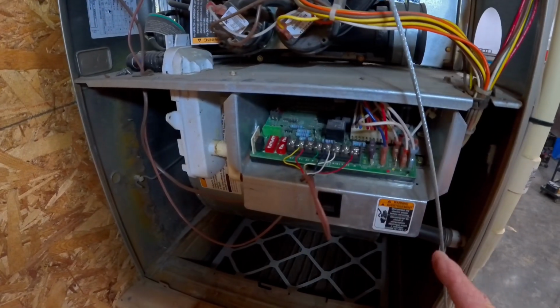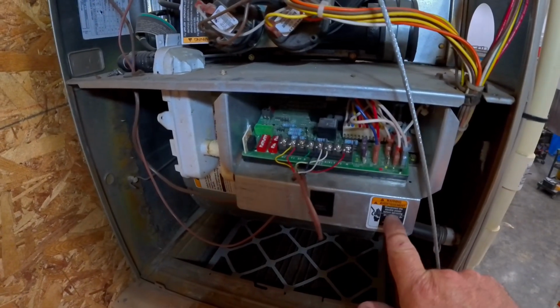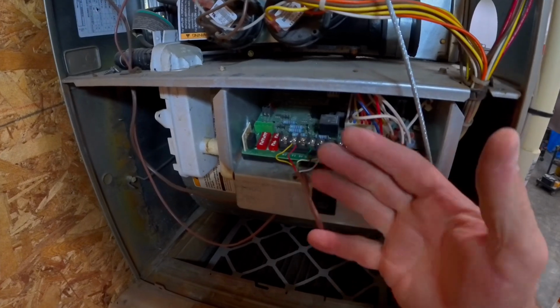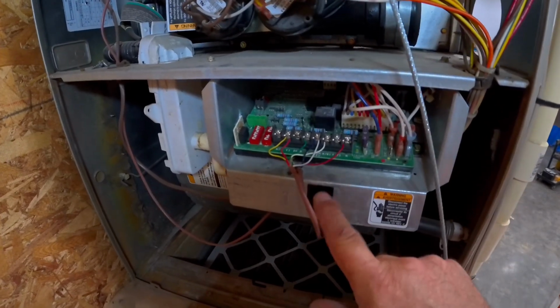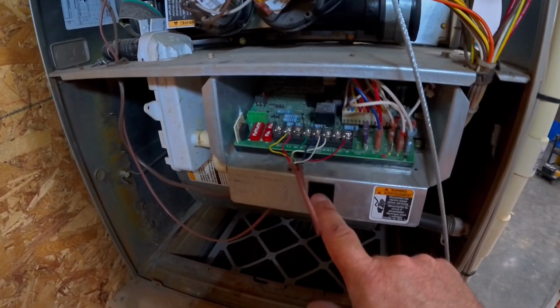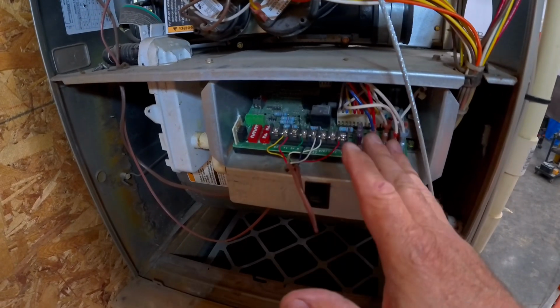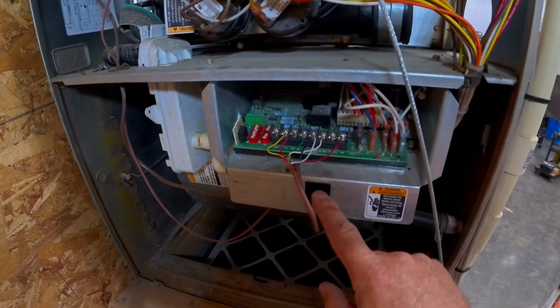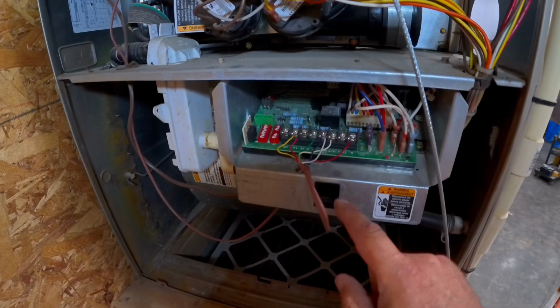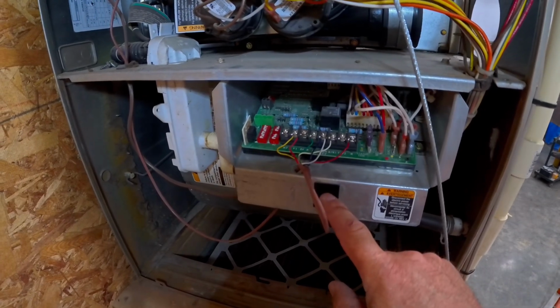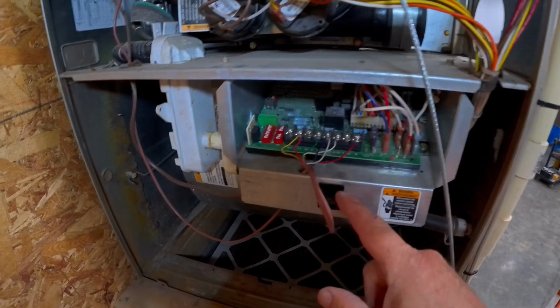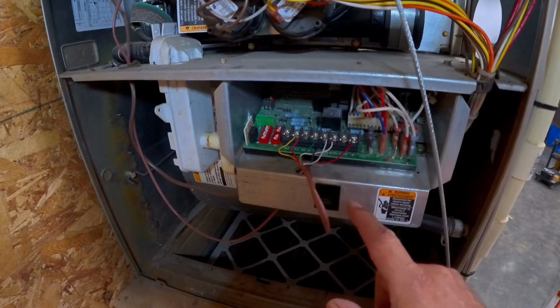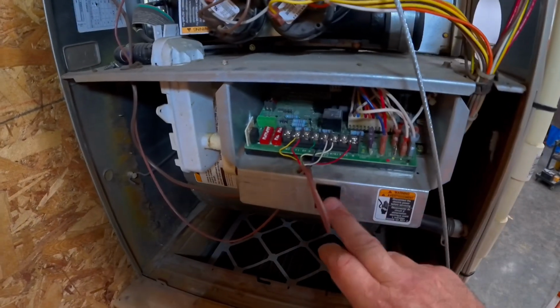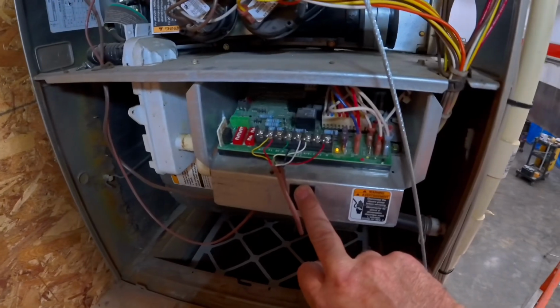But the biggest thing that I need to point out first is this disconnect right here. As soon as I took this service door off, it opened this switch up. This is a safety switch, so now there is no power anywhere inside this furnace because it's shut off at that. So to do any of our checks, we're going to have to bypass this switch simply by holding it in, or having somebody else hold it in, or putting a piece of tape across it to hold it in. But basically we need to close this, and you can see now we got power back on.